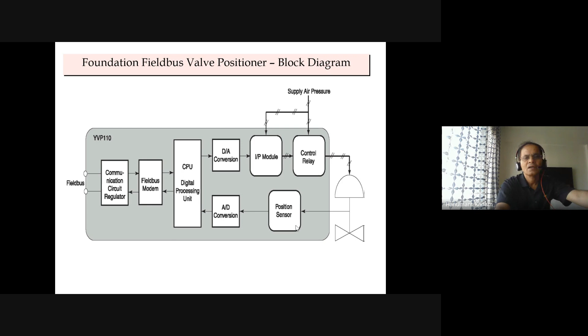So this is the block diagram of a smart valve positioner. You can see here the input position set point, input current or signal coming from the control room. Internally, whatever we have seen in the block diagram, the same PID position control, current to pressure converter is inside, and the pneumatic relay is inside. So all these are embedded inside the box. The position set point is coming also.